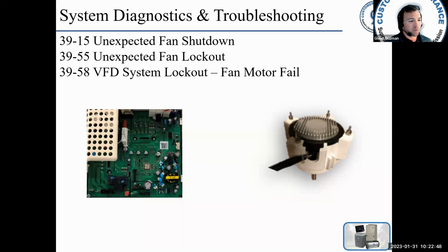The fault triggers a compressor and fan shutdown and then a VFD reset. Other fault codes will be present. Okay. If the demand is still present, try to restart and run normally. An intermittent open in the signal wire, the FG wire, could cause this fault. So, check your connections, check your plug, check your intermediate harness.